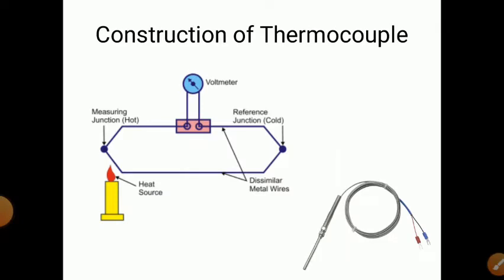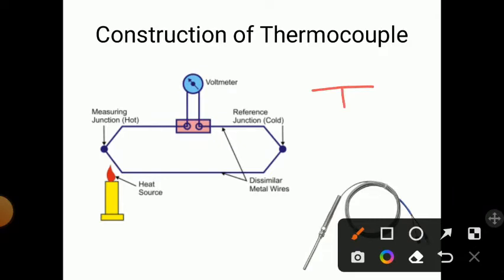A thermocouple is made up of two dissimilar metal wires connected together to form two junctions. One junction is called the hot junction and the second is called the cold junction. The hot junction is also called the measuring junction. As temperature difference occurs between the two junctions, a voltage is induced in the circuit.